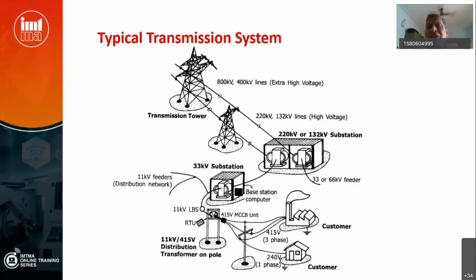Different states have different rules, but here in Karnataka, if the connected load is beyond 50 kilowatts, you must get the power at 11 kV. Why it is so, I will explain at a later stage. Basically, electricity is a state subject. Different states will have different rules. If the connected load in an industry is 50 kilowatt and more, he has to get the power at 11 kV and then step it down to 415 and use it for his loads. And again 415, if you use phase and neutral, then it will be 230, which generally we use in domestic loads. This is the basic schematic description of the whole distribution system prevailing in the country.